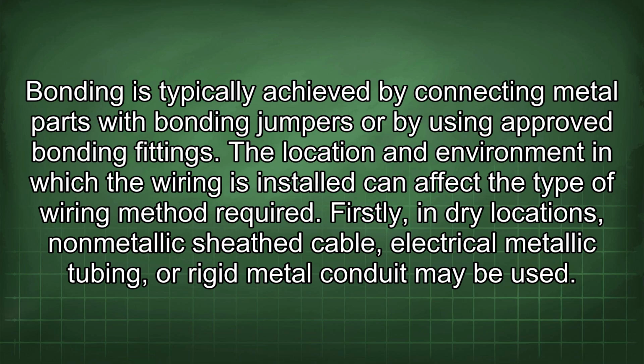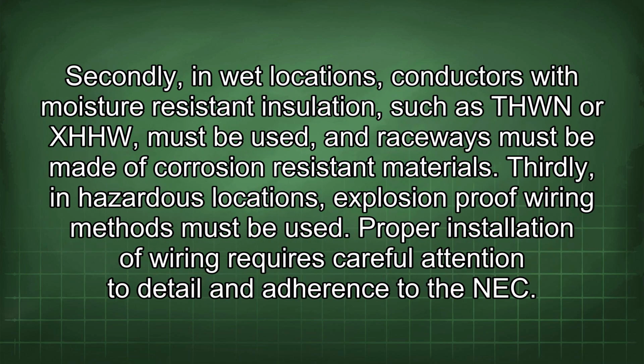The location and environment in which the wiring is installed can affect the type of wiring method required. Firstly, in dry locations, non-metallic sheath cable, electrical metallic tubing, or rigid metal conduit may be used. Secondly, in wet locations, conductors with moisture-resistant insulation, such as THWN or XHHW, must be used, and raceways must be made of corrosion-resistant materials. Thirdly, in hazardous locations, explosion-proof wiring methods must be used.